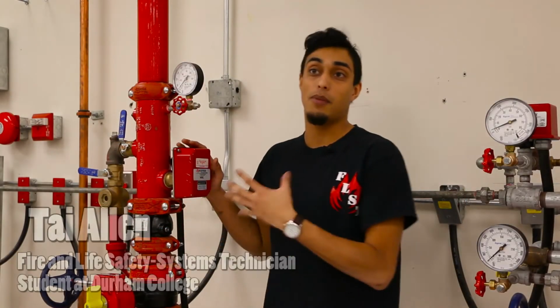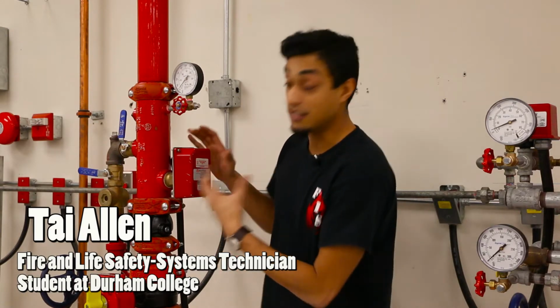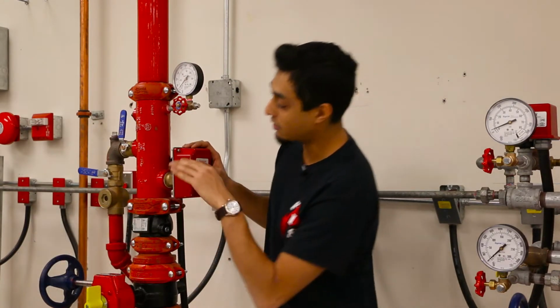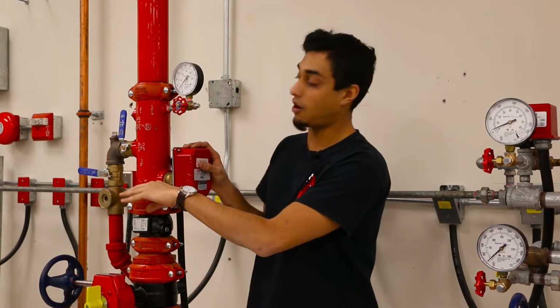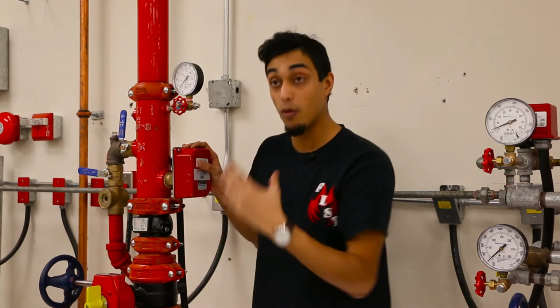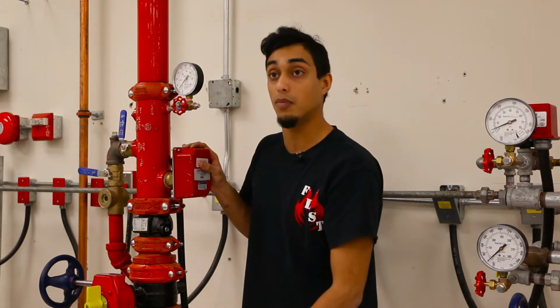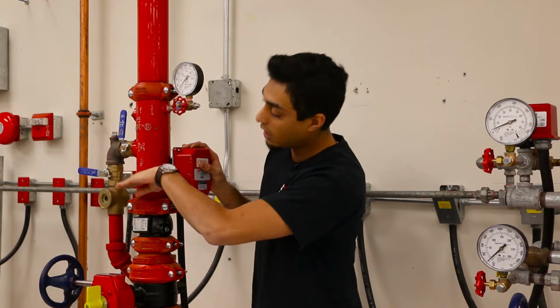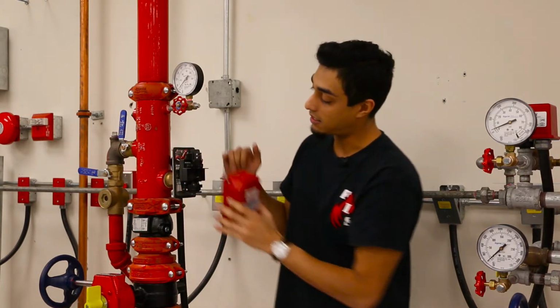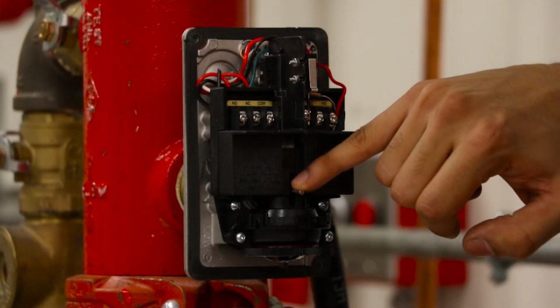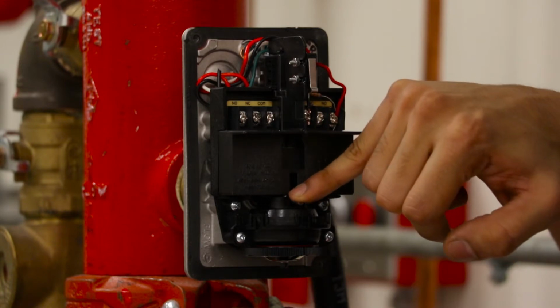What we have here is a paddle style flow switch. This is called a paddle style flow switch because there is a paddle positioned across our riser like so that when water is sent from our supply up through our system, it moves the paddle like so and sends this little lever at the back down and sends an alarm condition to our panel.